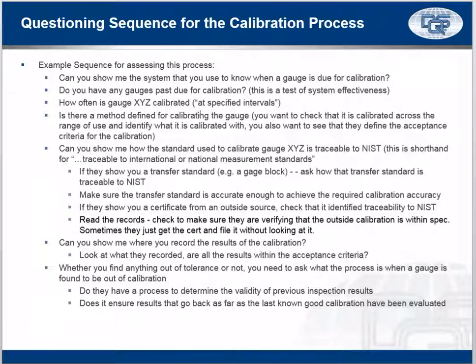Is there a method defined for calibrating the gauge? You want to check that gauges are calibrated across the range of use. A lot of times they'll say, oh, I take my caliper and I put it on the 1-inch block. Well, if I'm using that caliper to measure things that are a half inch, 1 inch, 10 inches, depending on the size of the caliper, maybe just a single point check is not going to be sufficient to know that it is calibrated across its full range. You also want to see defined acceptance criteria for the calibration. So when they take that caliper and put it on a gauge block, how do they know it's passing? How do they know it's failing? They have to define that acceptance criteria.